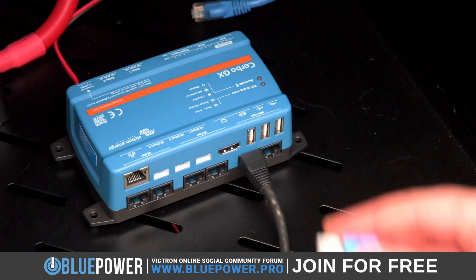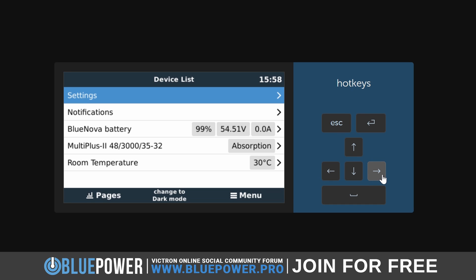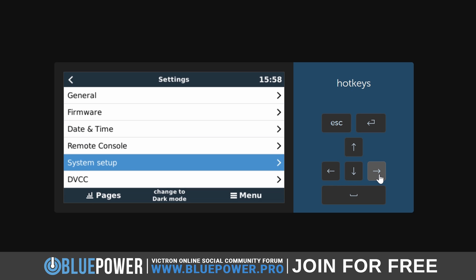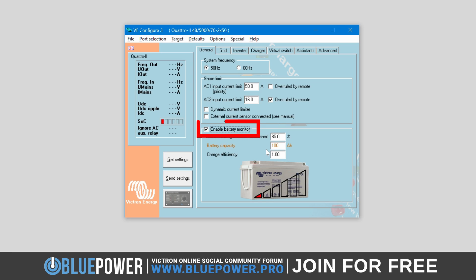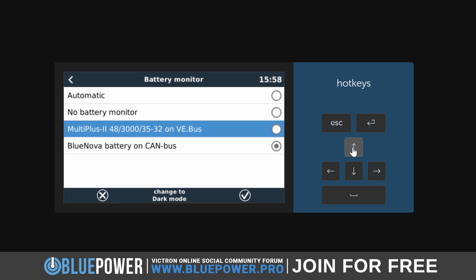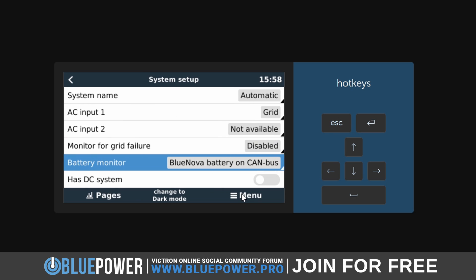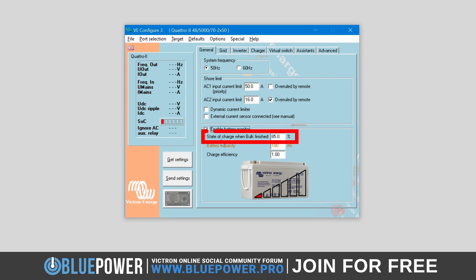If there is an external battery management system, it should take priority over this built-in fallback. Using a GX device such as the Cerbo, you can configure which system has priority within the Venus OS settings. Go to the Cerbo's device list via the remote console interface, then navigate to Settings > System Setup, and click on the Battery Monitor option to select which BMS takes priority. Note that the 'enable battery monitor' option must be enabled in VE Configure for your VE bus charger model to appear as an option here.